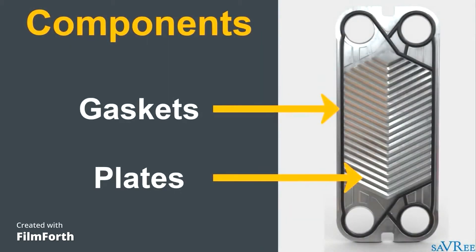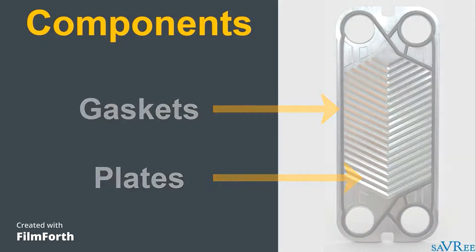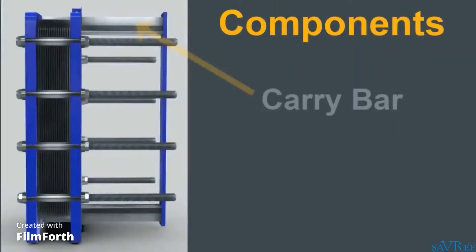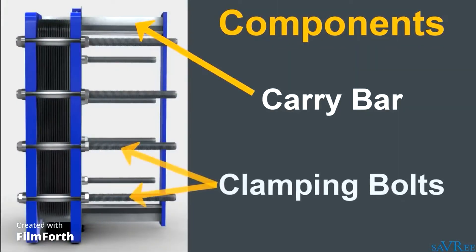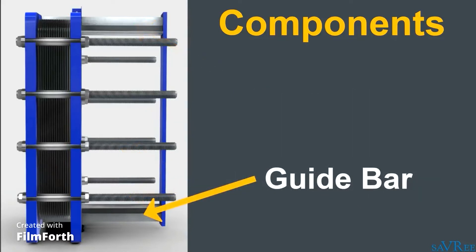Gaskets and plates are used to separate the flowing mediums and prevent them from mixing. The gaskets are adhered to one side of each plate only. The plates hang upon a carry bar and are pressed together using clamping bolts. When the plates are compressed together, they form a plate stack. A guide bar ensures the plates are aligned correctly when the plate stack is opened and closed.